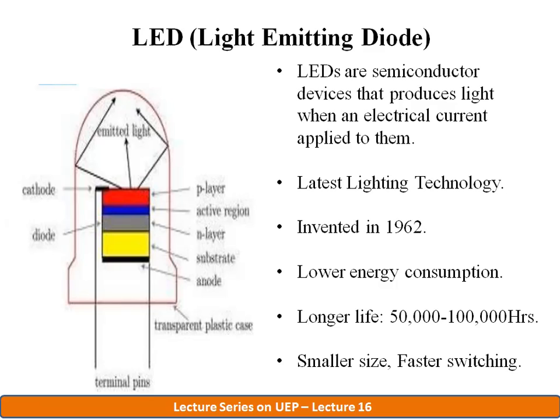LEDs have a very high correlated color temperature, often above 5000 Kelvin, producing a cold bluish light. However, white LEDs of about 2600 to 3500 Kelvin have improved significantly, now approaching the efficacy of CFLs. In addition to a warmer appearance, the LED color rendering also improves. Leading warm white LEDs are now available with a color rendering index, CRI, of 80, equivalent to the CFL.